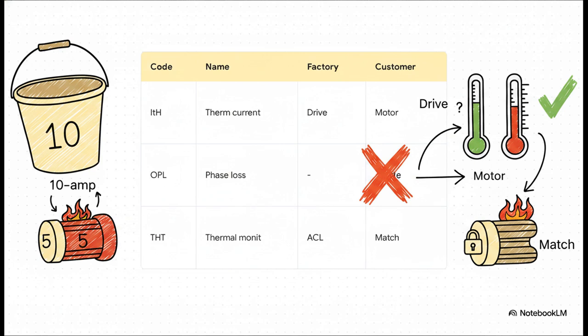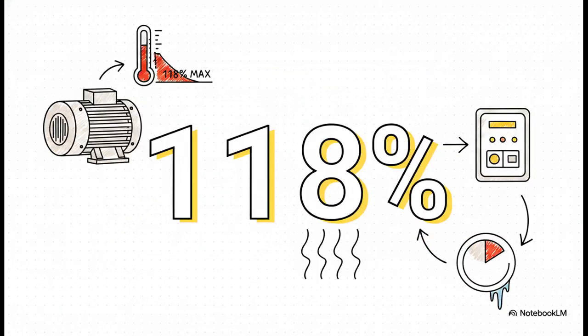Imagine you buy a 10 amp drive, but you only hook up a 5 amp motor. The drive's math thinks the bucket can hold 10 amps worth of heat. So if your 5 amp motor starts struggling and pulling 8 amps, the motor is literally cooking itself to death. But the drive? It thinks everything is totally fine because it hasn't hit 10 amps yet. You absolutely must change the ITH setting to match your specific motor's nameplate nominal current. No exceptions. The good news is, once that ITH parameter is dialed in correctly, the drive's math becomes incredibly precise.